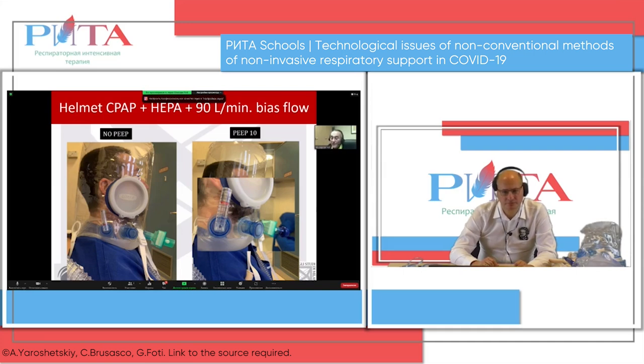You absolutely can trust it, and if you want to be very accurate, keep in mind that if you change the PEEP, it changes the FiO2. Because the higher the PEEP, the less powerful the Venturi system is. But the manufacturer provides tables for different levels of PEEP. So if you apply 10, look at the 10 table, and you'll have very good accuracy.